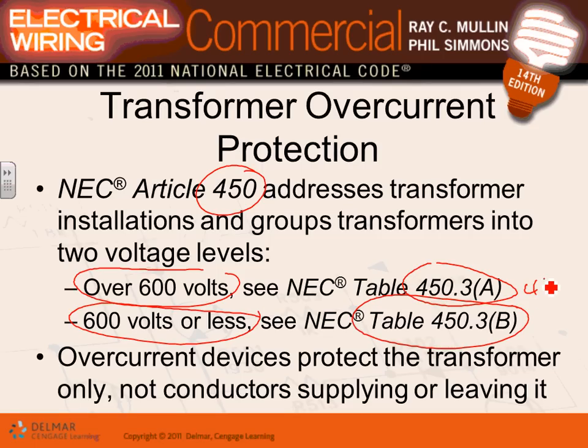So if you have a 480 transformer, 208/120, so 480 primary, 208/120, you're going to be using the B, the 450.3(B). So the overcurrent protection device that they use with the transformers is meant to protect the transformers, not the supplying conductors, not the conductors.